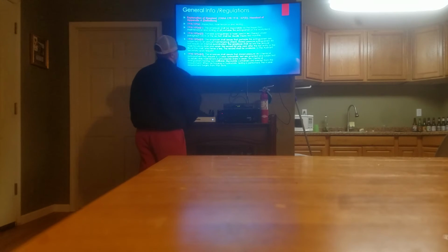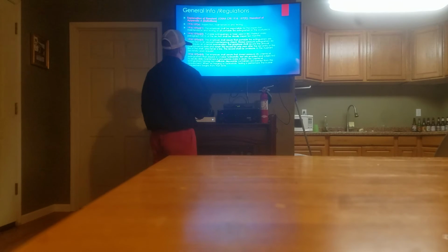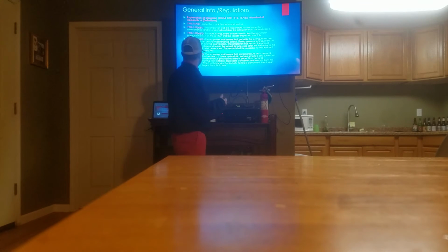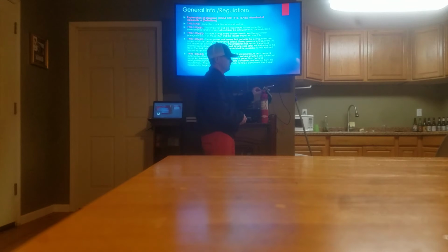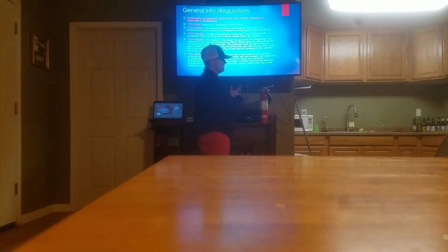Okay, so the next part says the employer shall assure that stored pressure and dry chemical extinguishers that require a 12-year hydrostatic test are emptied and subjected to applicable maintenance procedures every 6 years. Dry chemical extinguishers having non-refillable disposable containers are exempt from the requirement. When recharging or hydrostatic testing is performed, the 6-year requirement begins from that date. So every 6 years, they subject it to some maintenance procedures. They'll go inside there, and from that date, that's when the 6-year timer starts.